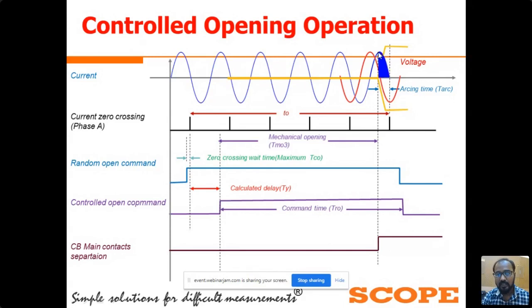After opening the CB contacts, once the system current goes to natural zero, at my cursor position the dielectric strength between the CB contacts is more than the system voltage. Due to that, there is no reignition of current after the system current goes to natural zero. So this is a controlled opening operation using the control switching device.